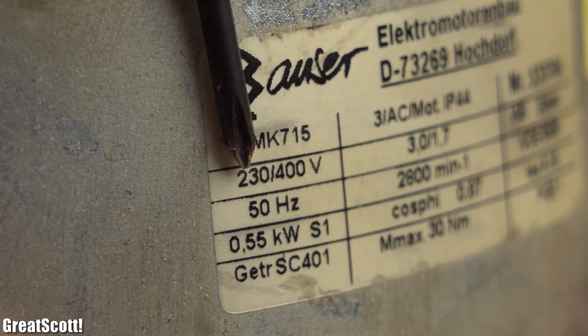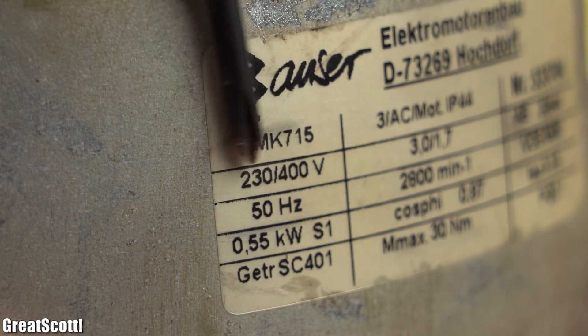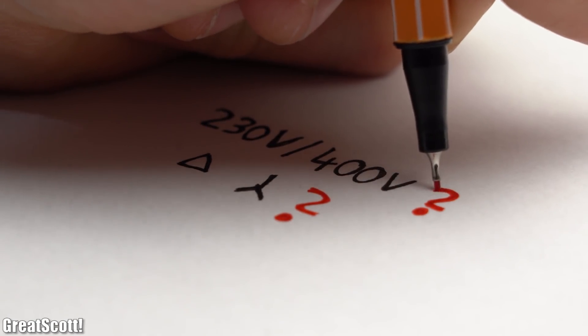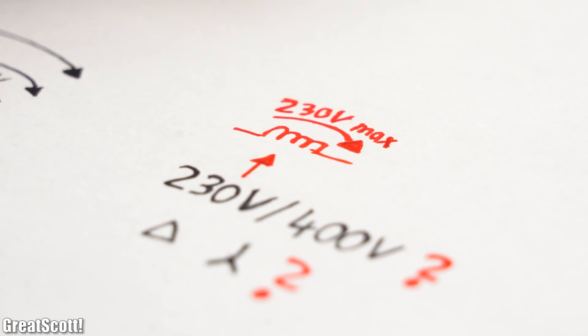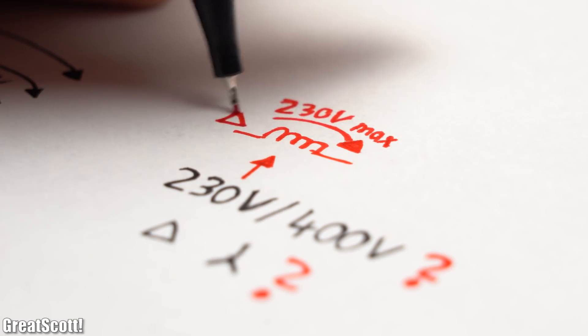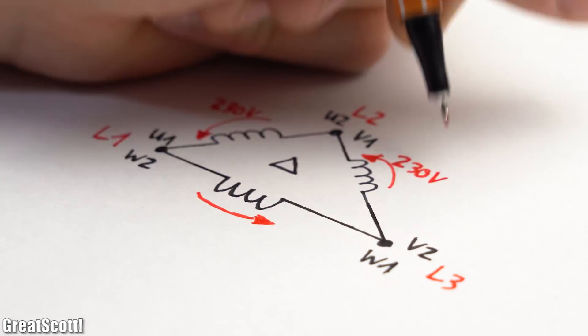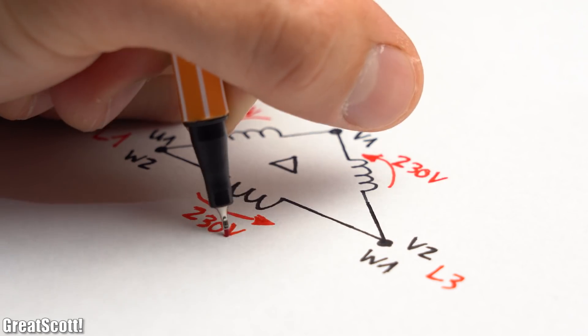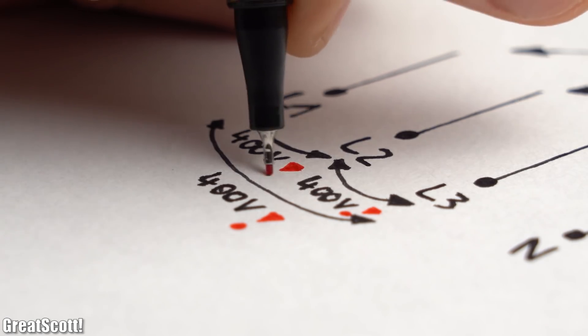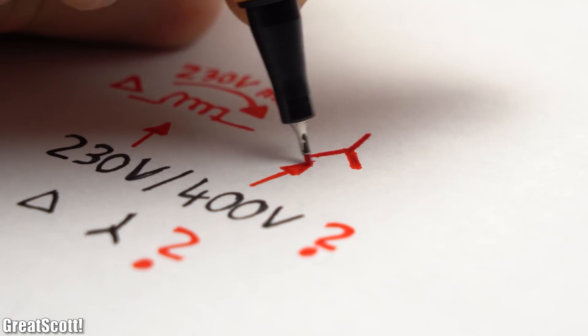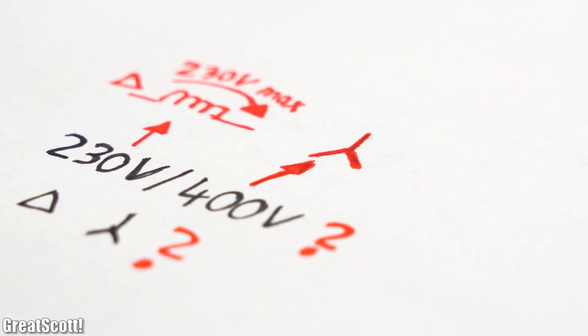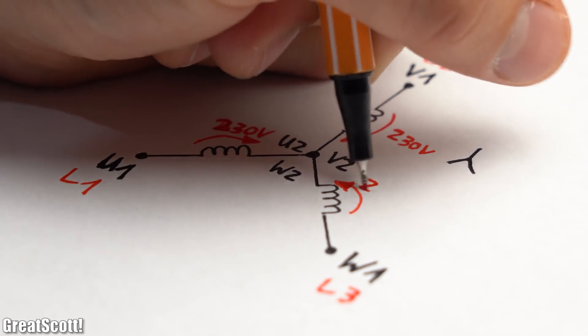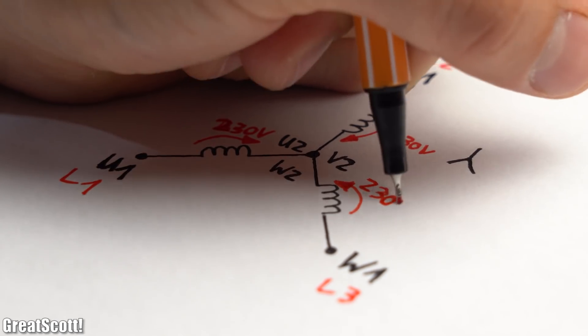But what does this 230V slash 400V mean? Should I use 230V or 400V? And with what motor coil configuration? Well, the first number basically says what maximum voltage the coils can handle and thus if we would have 230V between phases we could directly apply them to each coil through the delta configuration. But since we got 400V between the phases we have to follow the second 400V rating which says that you should use a star configuration at 400V levels since that will reduce the voltages across each coil to 230V.